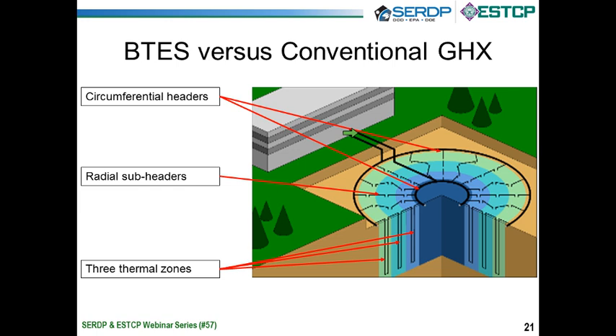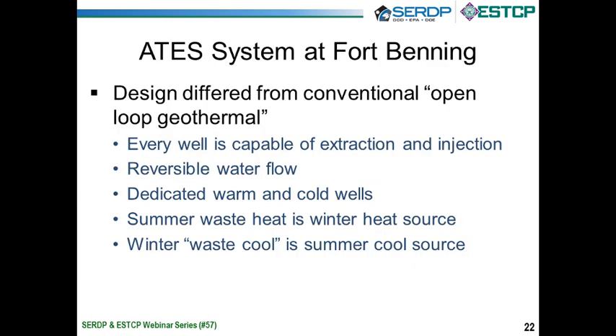In the wintertime, the building chills the water and our adiabatic dry coolers chill the water, so we reverse the flow. And at that point, cold water flows to the core, and we chill the core, the most important part to us, and then back out through the same boreholes in a reverse flow, and the water is gathered up in the circumferential header and back to the building where it's warm and can heat the building and we can dump the heat. So that is kind of the key thing here. We've got thermal zones, reversible flow, and that is what separates a BTES system from a traditional closed-loop system.